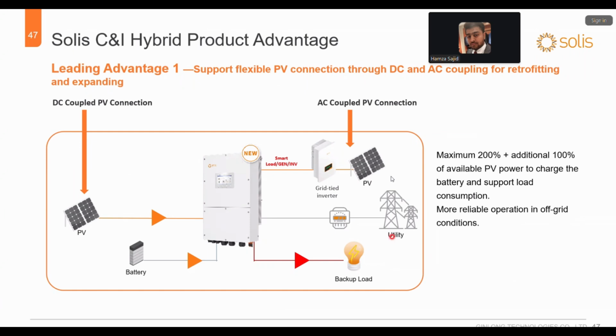Maximum 200 plus additional 100% of available PV power can charge the battery, support the load consumption, and give more reliable operation in the off-grid condition. Because if there is a 50 kilowatt on-grid inverter and a grid outage happens, it is not going to utilize any power from the PV. If it is attached with the hybrid inverter, it can work directly, and together they can support battery charging and backup load. So it will help the customer a lot.